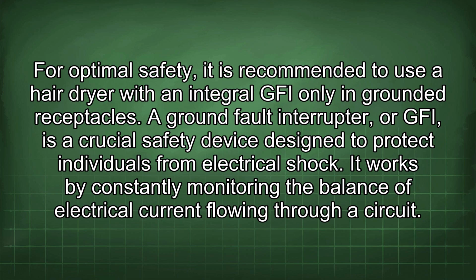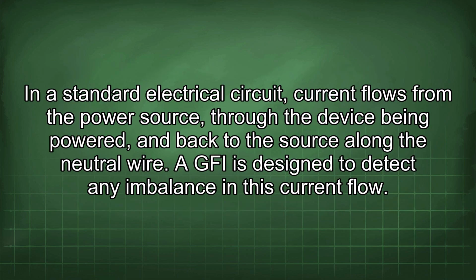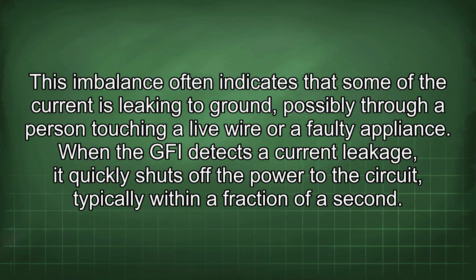A ground fault interrupter, or GFI, is a crucial safety device designed to protect individuals from electrical shock. It works by constantly monitoring the balance of electrical current flowing through a circuit. In a standard electrical circuit, current flows from the power source through the device being powered and back to the source along the neutral wire. A GFI is designed to detect any imbalance in this current flow. This imbalance often indicates that some of the current is leaking to ground, possibly through a person touching a live wire or a faulty appliance.